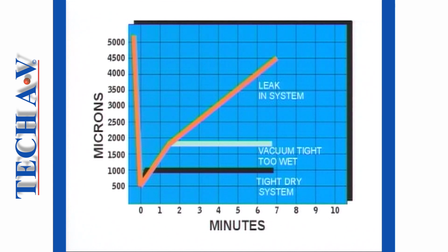The worst case is that pressure increases continuously, which indicates a leak, and we'll need to go back to a full pressure and leak test routine and repair the leak.